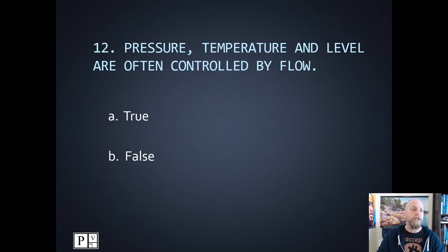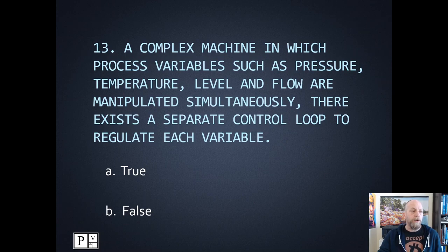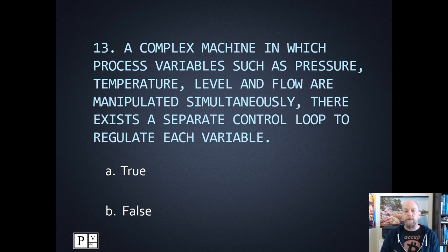Number twelve: pressure, temperature, and level are often controlled by flow. That's true — the most common actuator is the valve, so pressure, temperature, and level are usually controlled by the opening and closing of a valve. Number thirteen: in a complex machine where process variables such as pressure, temperature, level, and flow are manipulated simultaneously, there exists a separate control loop to regulate each variable. You're not going to mix those signals together — every pressure, temperature, level, and flow will have a completely separate control loop. That would be true.